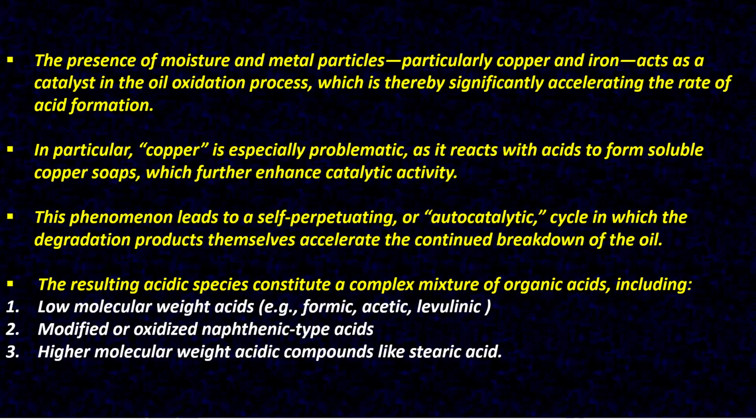The presence of moisture and metal particles, particularly copper and iron, acts as a catalyst in the oil oxidation process, thereby significantly accelerating the rate of acid formation. In particular, copper is especially problematic as it reacts with acids to form soluble copper soaps, which further enhance catalytic activity. The phenomenon leads to a self-perpetuating or autocatalytic cycle in which the degradation products themselves accelerate the continued breakdown of the oil.